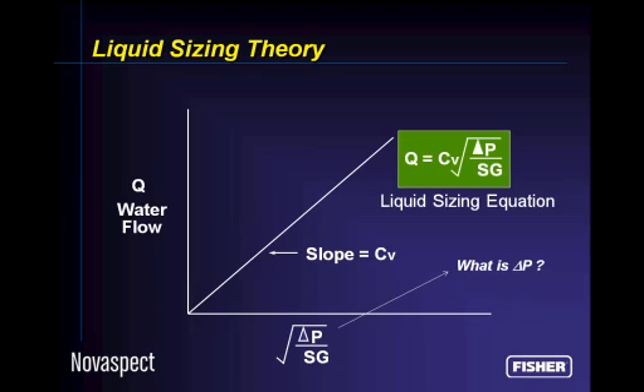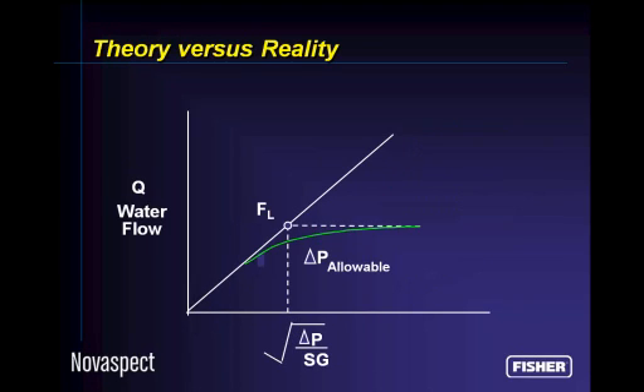That, in theory, is a great idea, but unfortunately, in reality, that's not what happens. What happens is that as differential pressure increases more and more, we reach a point where theory falls apart. And what happens is we reach a condition called choke flow. And at choke flow, vaporization is occurring. Water, let's use that as an example, the fluid is flowing into the valve, and we drop below the vapor pressure of the fluid, and vaporization, we boil, to put it in simple terms.